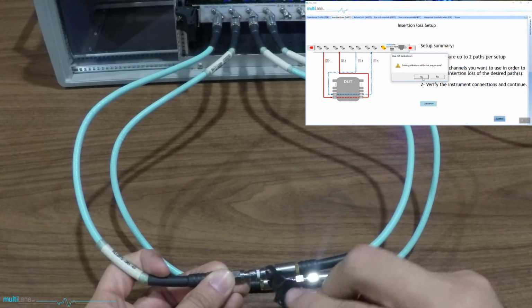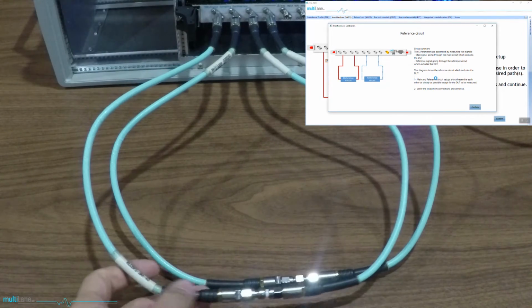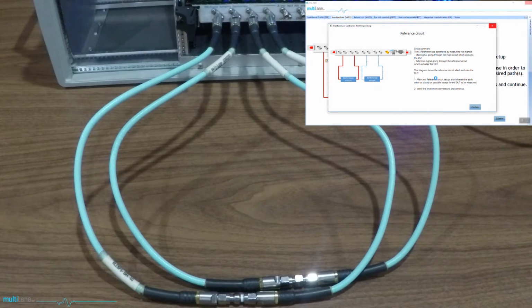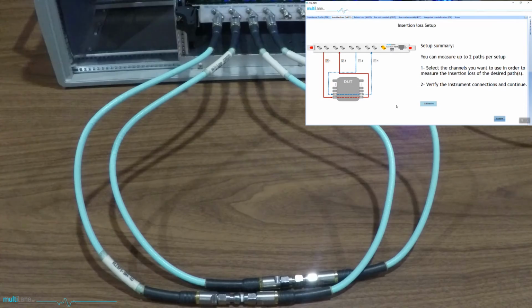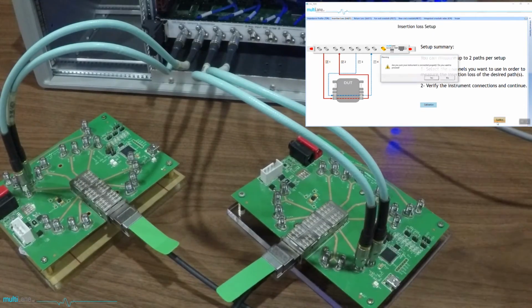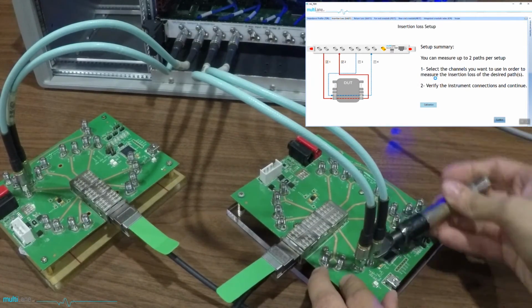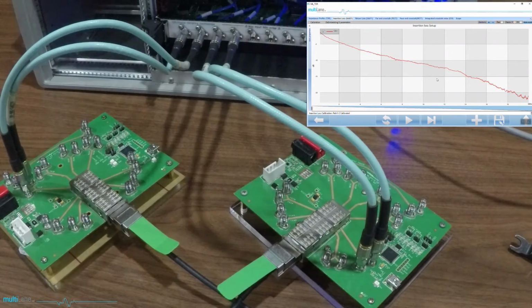Calibration for insertion loss measurements is performed by connecting together channels 1 and 2 of the ML4025-TDR. The setup differs from that of TDR measurements by having channel 2 connected to RX1 of the second MCB instead of 50 ohm termination.